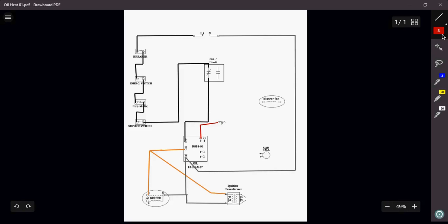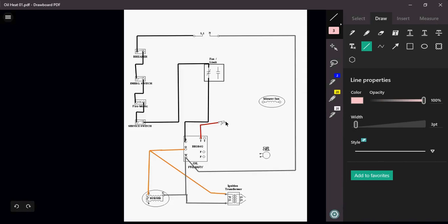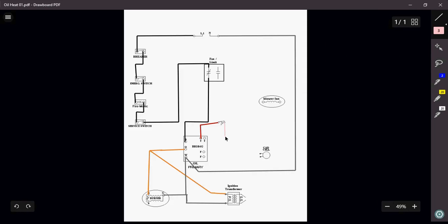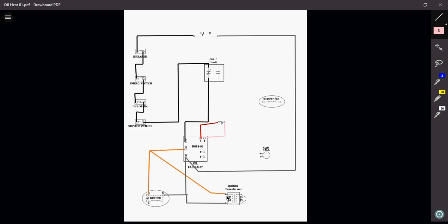And that is going to be like this. I'm going to bring power in. I'm going to change the color to a different color. It's just going to come right back in. So why is that working? Well, the primary control is really nothing more than a relay that is just going to open and close a set of contacts in there to make and break my oil terminal to turn my burner on and off. So, once my thermostat closes, I'm energizing the components inside my primary control, which will now, in turn, send my 120 volts out to my burner and my ignition transformer.